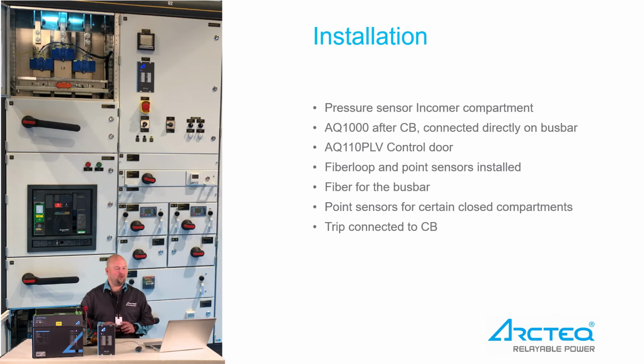So most typical installation places AQ1000 as close to the main circuit breaker as technically possible. For the new builds it is almost always possible. For the retrofits you may have to consider also other locations, but as close as technically possible.